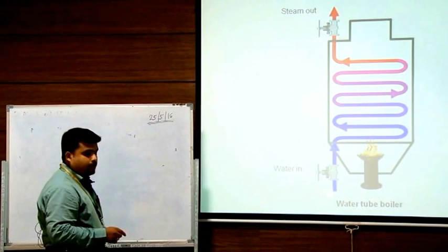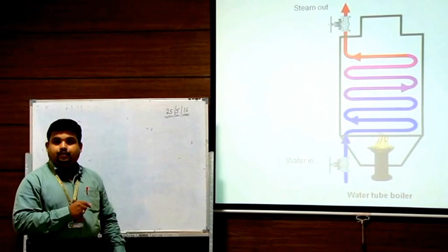Now we have to take one point over here, that in this particular journey of a flame and its flue gases, all the heat is being recovered in the water tube boiler. Now this particular pipeline is almost consistent, with no escape or addition of any other medium. So what happened is the pressure which is developed for the steam is much higher, right, and we can have a continuous output from this type of mechanism.